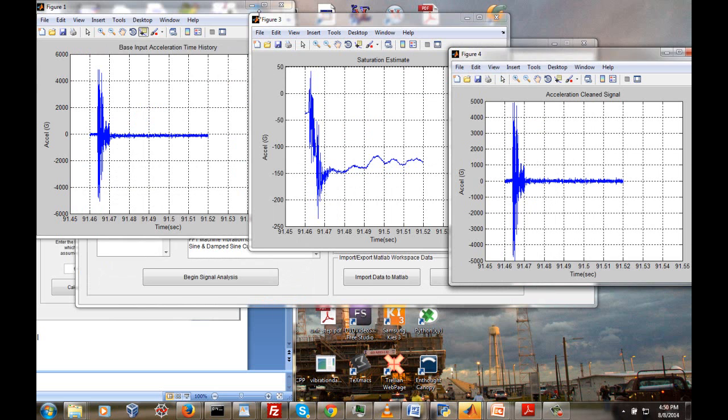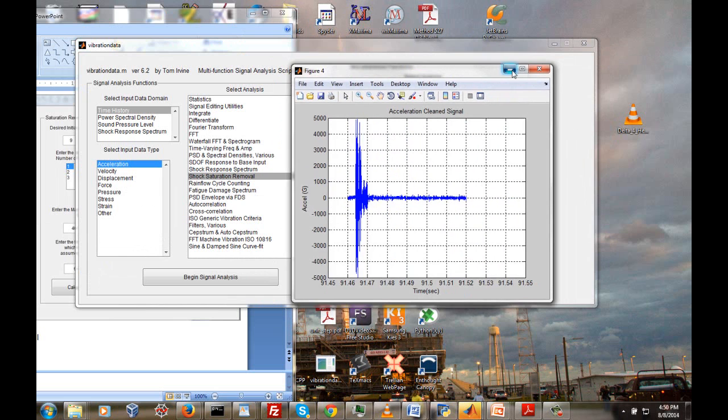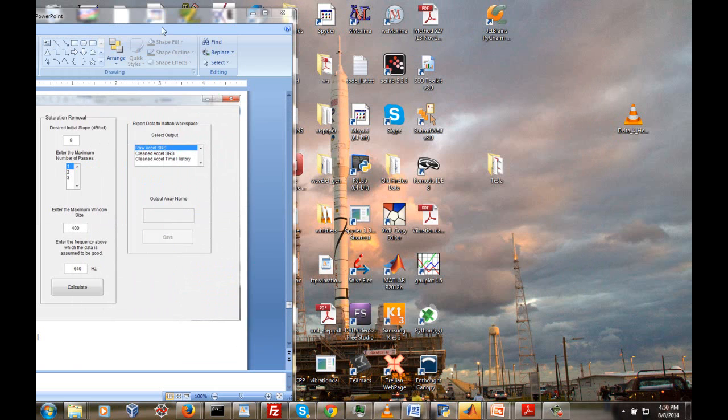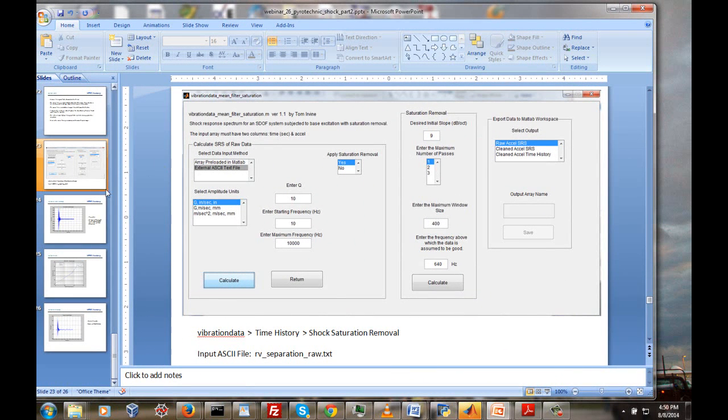Well, the best we could do would be to prevent this error in the first place, but after the fact, that's the best we can do. And there are actually some vendors that make accelerometers nowadays that have built-in mechanical low-pass filters and/or built-in electrical low-pass filters that help mitigate both the potential for aliasing and the potential for the accelerometer crystal natural frequency to be excited.